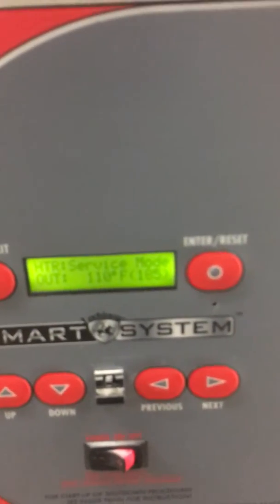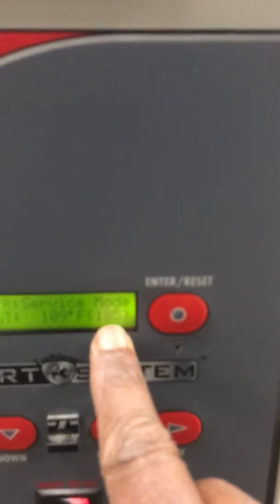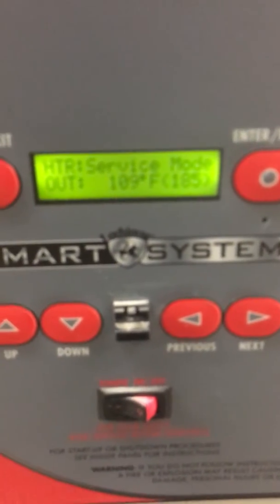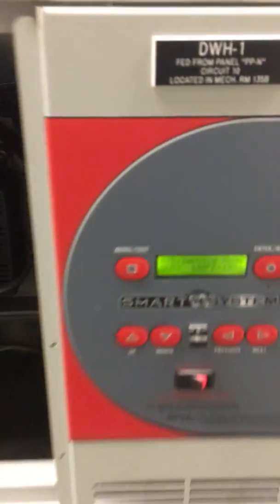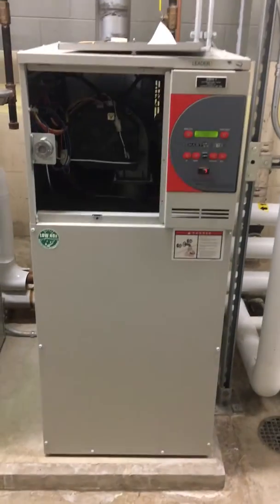Now, let's wait for a second. Let's let the actual temperature, my out temperature, go up. It's at 110 now. And my set temperature, my set point is at 185. And let's wait for it to go up. Wait. It's not going up. That's my fan. Let's slip off. Let's just let you look at the whole water heater itself. This is a standby system. So, I have two water heaters for this industrial building.